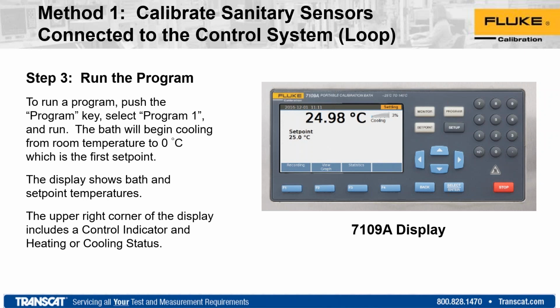The other thing that's really nice about these is that when you're setting up those program limits, you can actually set a stability and set point limit. So the bath won't start the soaking process until it's reached those stability limits, and then the timer will begin to count. This is pretty useful if you've got, say, one person doing multiple tasks on a job. It helps semi-automate it, to free up some of their time.